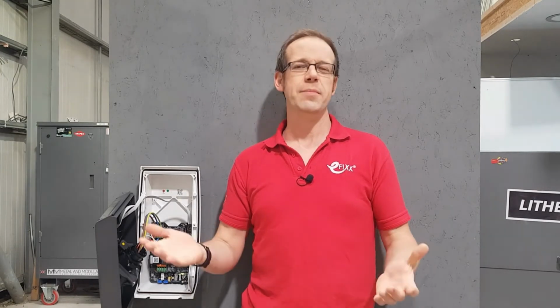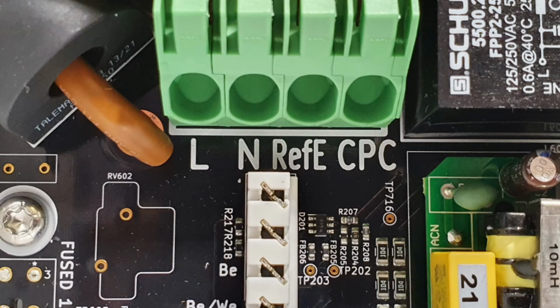The paragraph in A722.4 goes on to outline some precautions of the electrode positioning to make sure the voltage on the electrode isn't affected by any bonded building metalwork entering the ground near the rod. For many domestic properties though, you'll find plastic incomers for the gas and water, and very likely no structural steelwork either, so it's not too much of a problem. The Indra Smart Pro charger allows you to use this method and has a terminal for connecting the reference earth electrode, as you can see here.